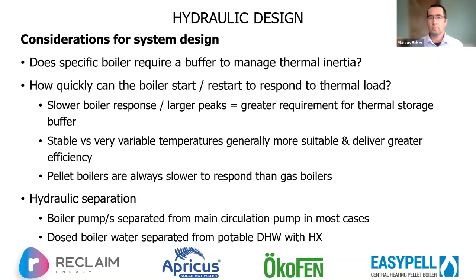So that's it for plant room design. If we just have a quick look at hydraulic design, the questions to ask really are whether the boiler that's specified is going to need a buffer. We looked at that last session. Some of the designs of pellet boilers do require a buffer to manage their thermal inertia. How quickly will the boiler respond? And therefore, we're going to have greater thermal storage if they're not particularly responsive, or if we've got very, very peaky demand, because in general, pellet systems biomass doesn't cope particularly well with very, very peaky demand. It'd be better if we can smooth it off a bit.